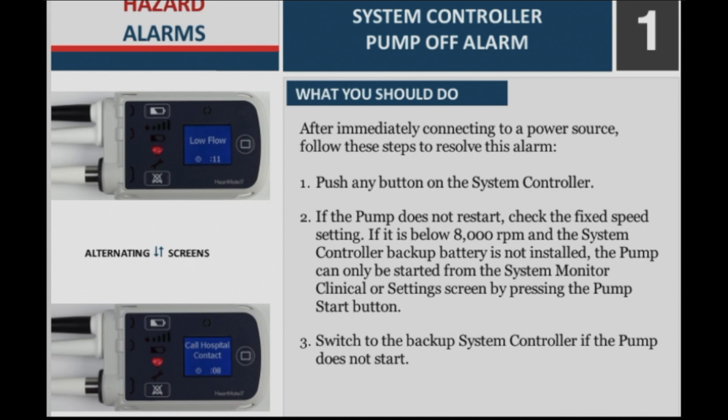Step 1: Push any button on the system controller. Step 2: If the pump does not restart, check the fixed speed setting. If it is below 8000 RPM and the system controller backup battery is not installed, the pump can only be started from the system monitor clinical or settings screen by pressing the pump start button. Step 3: Switch to the backup system controller if the pump does not start.